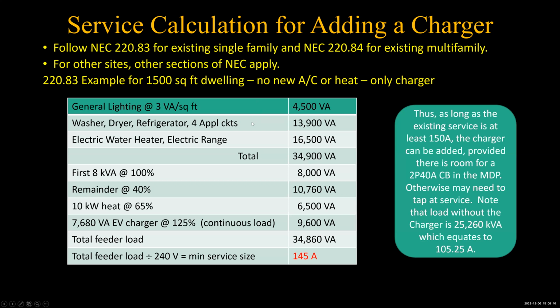And one of the things that's really going to mess it up is if you got a tankless water heater at 12,500 watts or something, that may push you up to needing to upgrade the service. Good possibility. But otherwise, as long as there's room for a 2-pole 40 amp circuit breaker, fine. Otherwise, you may need to do a tap, maybe a line side tap or some other way of tying it in, or splitting and putting another sub panel, whatever you have to do to add that.